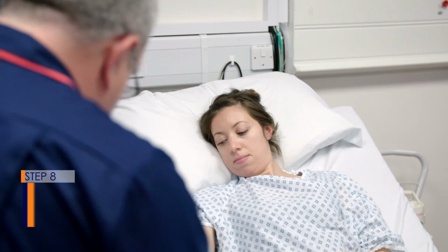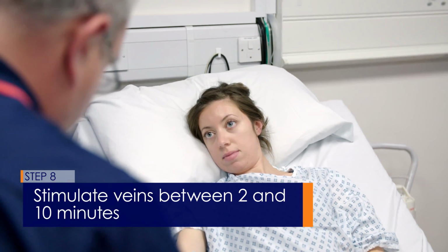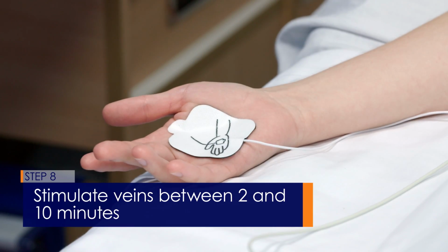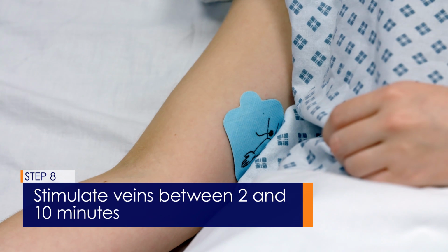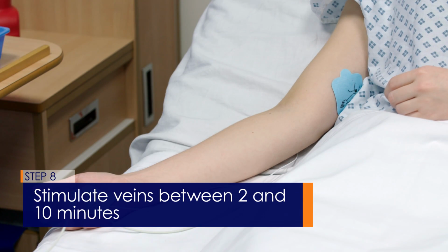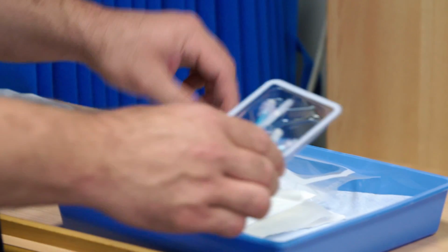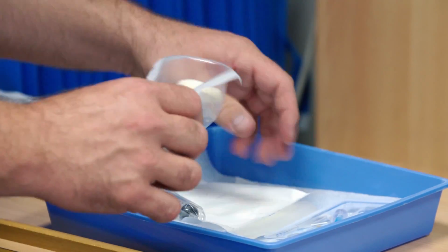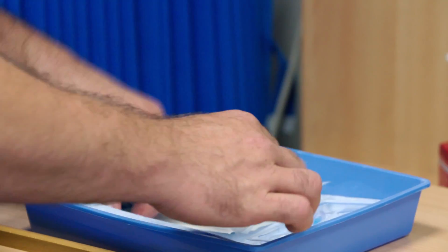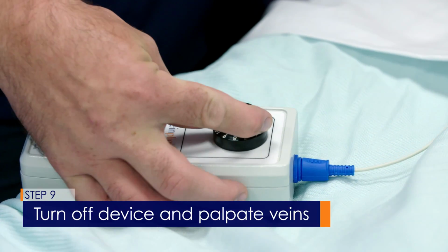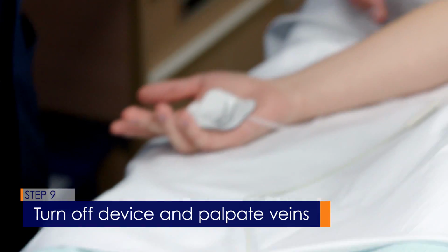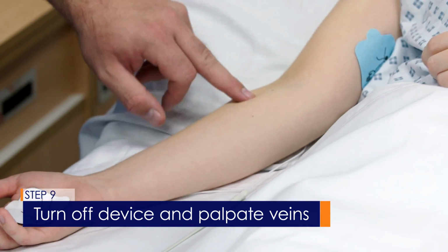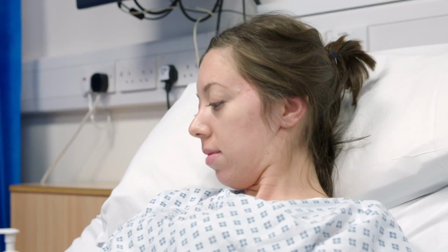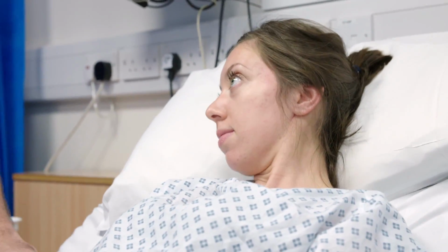Under normal circumstances, you will deliver stimulation for at least 2 minutes, but no more than 10. The device will automatically shut off after this time. While stimulation is being applied, prepare for the procedure. After approximately 2 minutes, turn the device off and palpate the veins. If the veins need further stimulation, you can turn the device back on. Never attempt venipuncture while delivering stimulation.